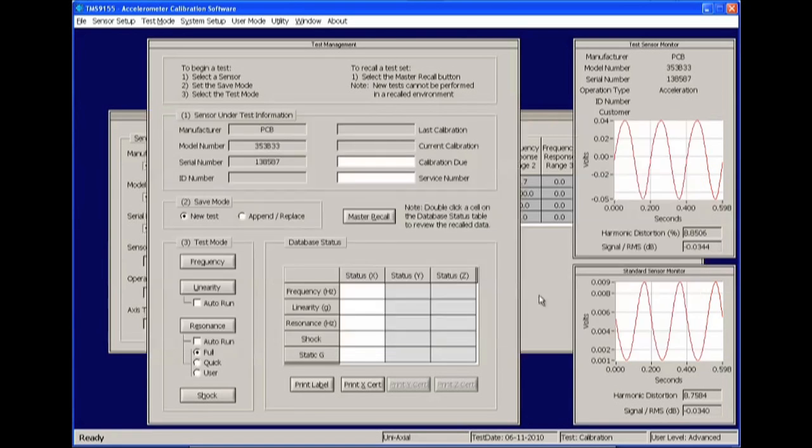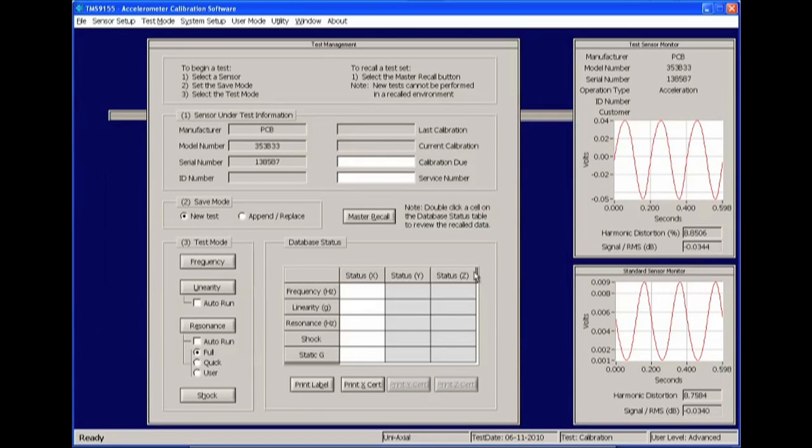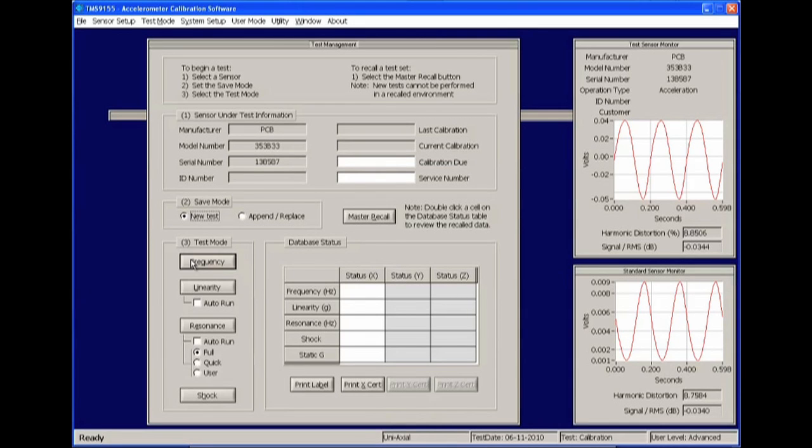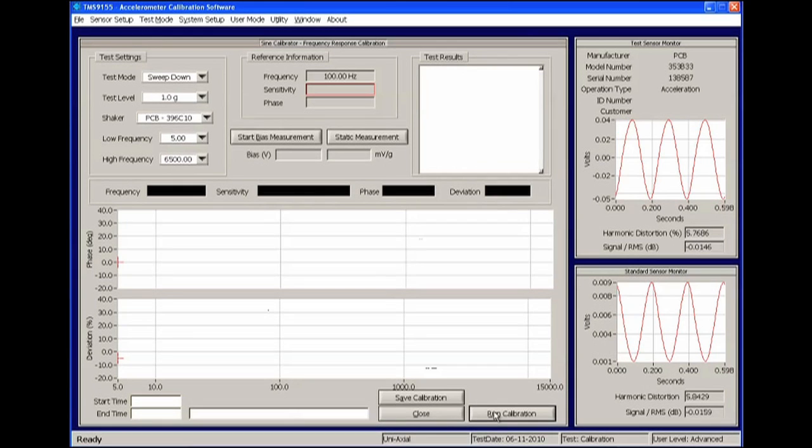Once you've returned to the main software panel, click the Frequency button. To run a calibration, update the test parameters such as Frequency Range and Test Level by using the drop-down menus located in the upper left corner of the software panel.